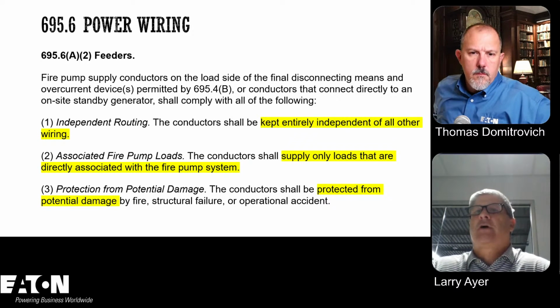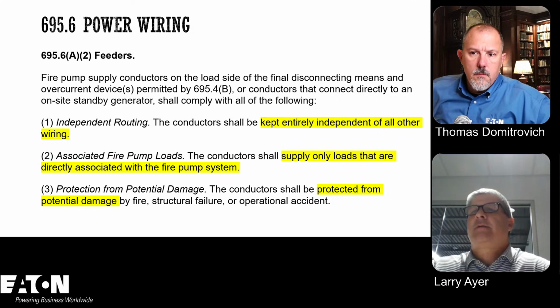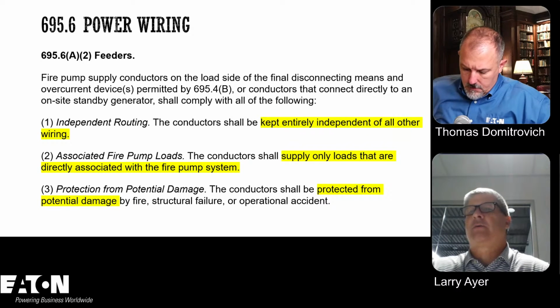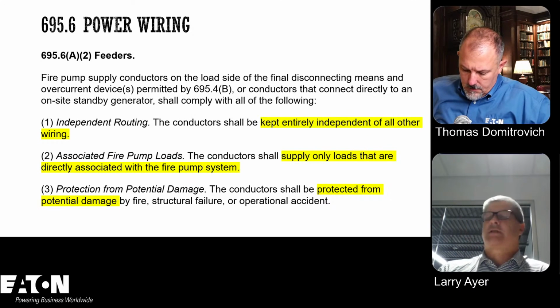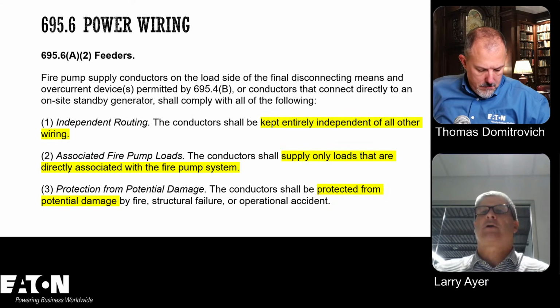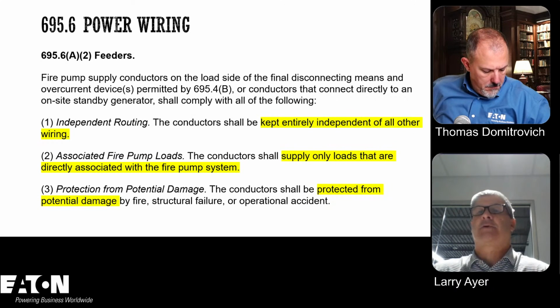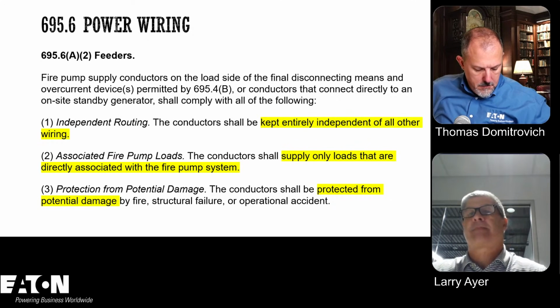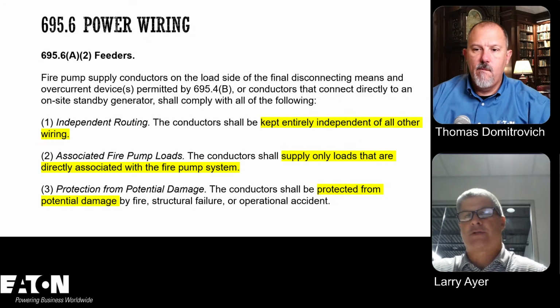By the time you're going from that disconnect to your fire pump control room, these rules, as you're putting them up on the screen: one, you have to have independent routing. You can't really put it with other types of wiring. You have to keep it independent. The conductor shall supply only loads that are directly associated with the fire pump system. So you can't mix and match other types of HVAC equipment or whatever. The feeder has to be only for the fire pump system, and you shall protect it from physical damage. We don't want anything to happen to that feeder because if it has to be called on in the case of a sprinkler going off, we need to make sure that it is able to do so and nothing's going to damage it. But I think the most important ones are on the next slide.